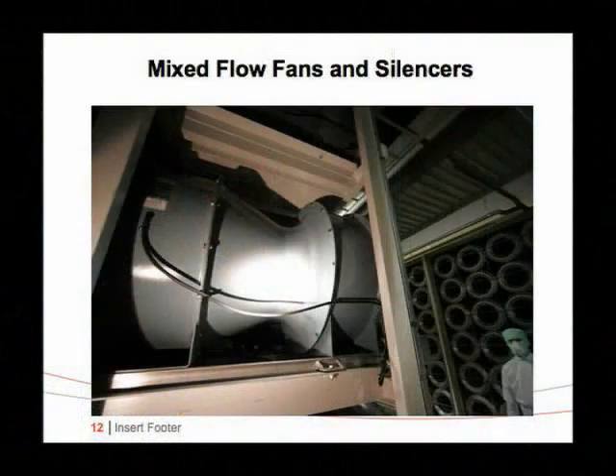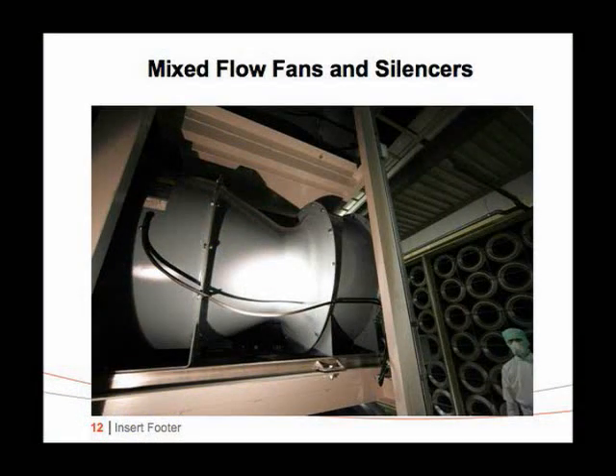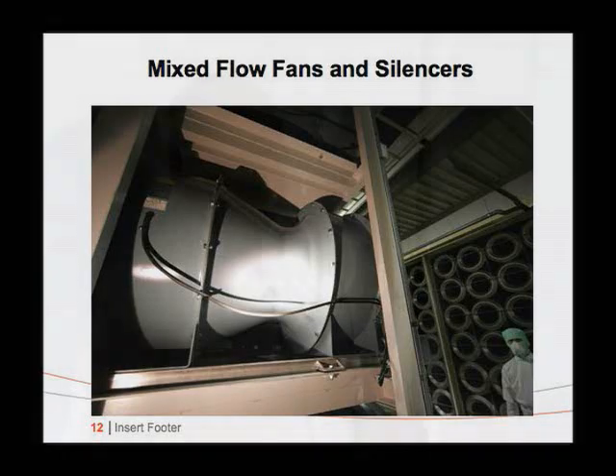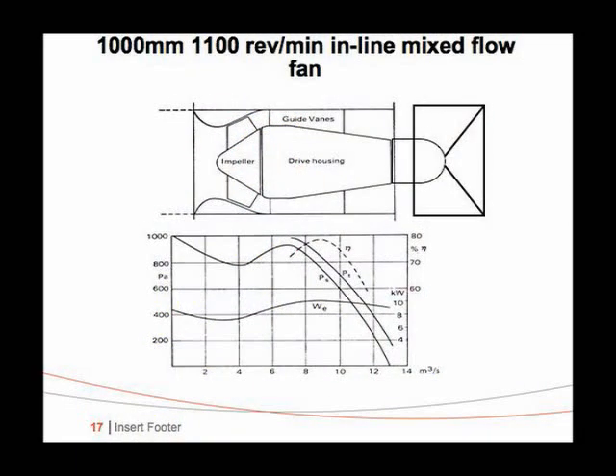You take a picture of this with my Nikon D2X, of course. And what is interesting is, has the aerodynamic efficiency of the fan been improved? So you look at the inlet to a mixed flow fan. I'm not a fan engineer, but you don't get a nice bell curve from here into the fan inlet. You get this square edge just in front of the blade, and man, that kills blade efficiency. I don't understand this, but you look at the business end, the air comes out through a set of dampers and then into cooling coils. This fab is, I think, 2 or 3 million CFM of air, so that's a lot of horsepower in the fans.